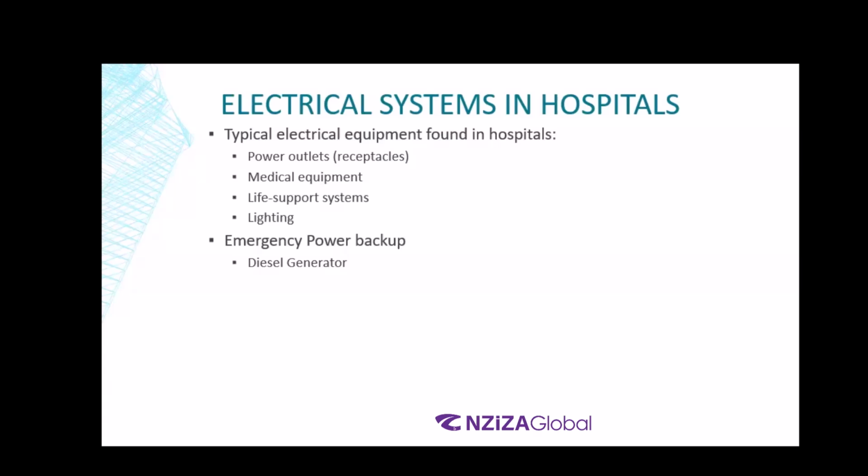It has an automatic transfer switch, which works on the principle of electromagnetism, that will change its direction from the utility to the diesel generator when there is a power outage, right? Yeah. That entire process will take anywhere between 1 to 10 seconds.